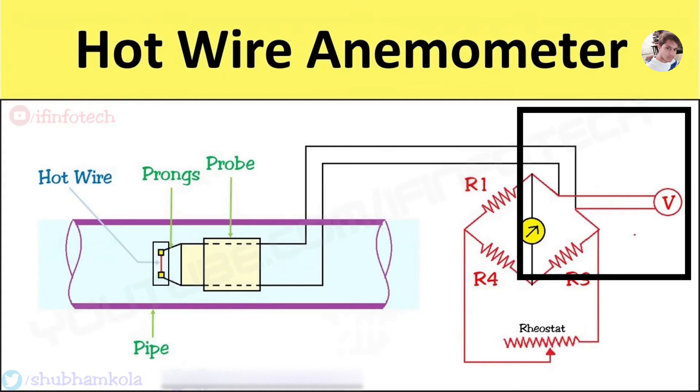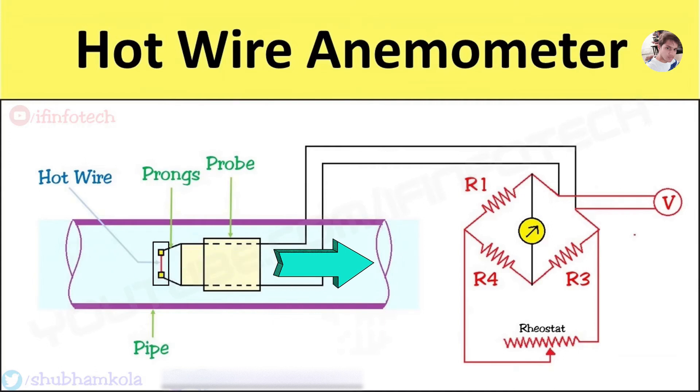The wire is heated by the passage of current. When the device is exposed to fluid flow, heat is dissipated by the wire through convection, causing a drop in temperature and consequently a change in resistance. Heat loss depends on velocity and the specific heat of fluid flow.